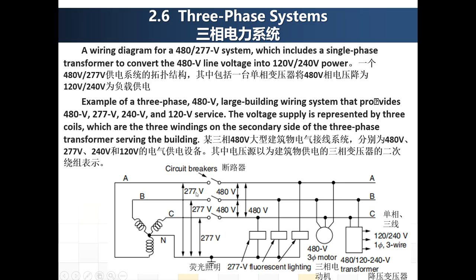The phase voltage is 277 volts. The line voltage is 480 volts. The 480 volts is used to supply power for the motors, and the 277 volts is used to supply the fluorescent lighting system. And between each phase, on the line voltage, we add another transformer. This is a single-phase transformer to generate 120 volts and 240 volts, which is used to supply the loads with a lower voltage.